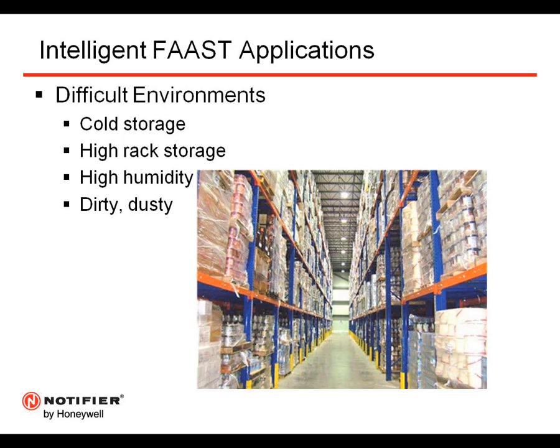Same could hold true for high humidity areas, if you're trying to protect a space where the humidity levels are above what the listed humidity levels are for a spot-type detector, as well as dirty and dusty environments. And another application is going to be high rack storage. And high rack storage brings a number of challenges associated with it.